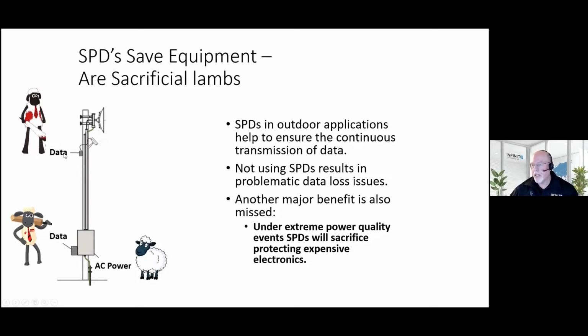So you'll have data protection at one end of the data cable near the equipment on the tower top and at the source, let's say near an Ethernet switch. And the reason for that, again, is induced surge current. Surge protectors have a sphere of influence of about 40 feet, so anything beyond 40 feet is a problem. And with data cable specifically, it's not uncommon to have 100 feet, 200 feet of data cable running up a tower. So that data cable itself is the source of the surge.